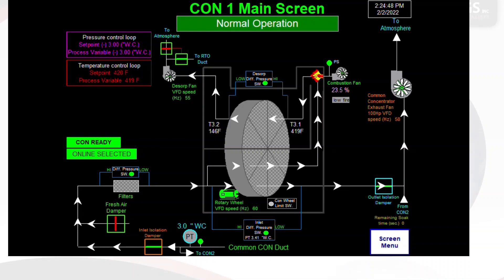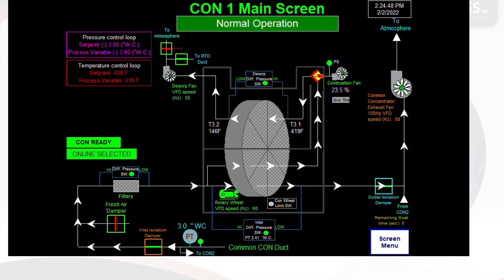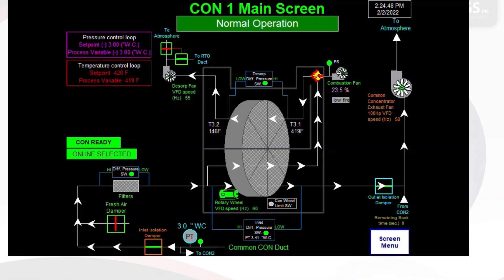A VOC concentrator takes airstreams that have very dilute amounts of VOCs in the airstream, and airstreams that are ambient temperature or cooler, and those are the perfect applications for a VOC concentrator. The type of VOC is important as well. It can't be a condensable VOC, it can't be certain types of alcohols that don't adsorb well onto the wheel. We'll talk about that a little bit later, but let's look at the operation of it.